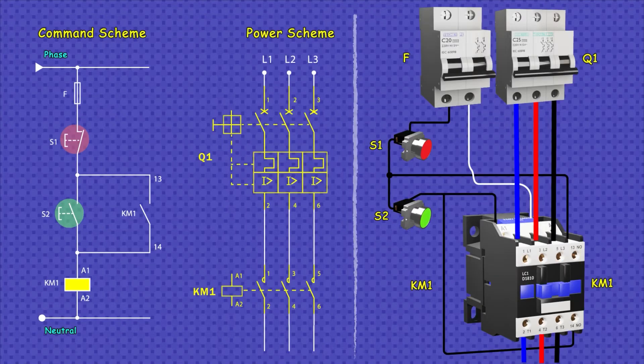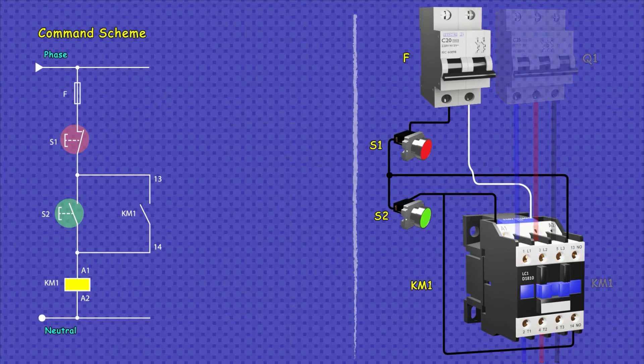The most basic diagram that can be made to use a self-latching contactor is the one shown, where on the left side are the control and power diagrams, and on the right side is the circuit represented with physical elements. The control diagram is made up of the following elements: a thermomagnetic switch, although the symbol indicates that this must be a fuse, a normally closed stop button, a normally open start button, and the contactor coil that would be KM1.